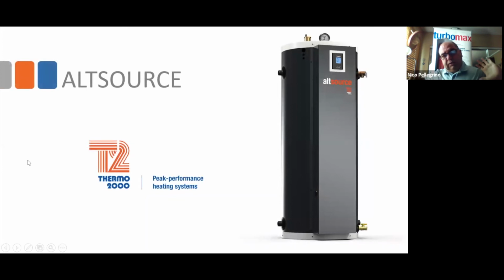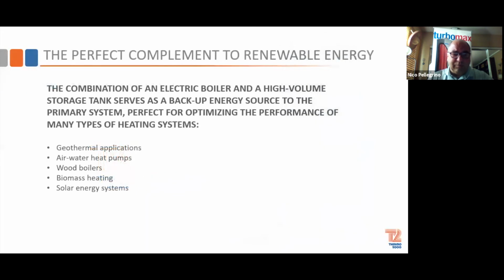So this one is one that I like really a lot because of the fact that the name says it all. It's alt source. And the reason being is because it can be married to geothermal, air to water heat pumps, wood boilers, biomass, solar, anything that makes hot water. This can be a backup to the energy source and be able to help in the performance of the system.